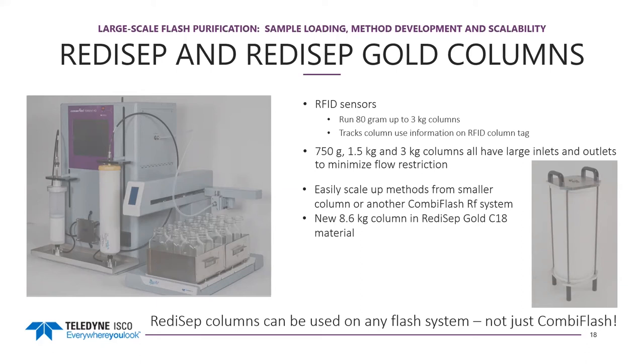All of these columns can be used on any flash system — not just on the CombiFlash, the next gen, or the RF+. You get the advantages of RediSep Gold media, including spherical particle size and smaller particle size for maximum loading. Going from RediSep regular to RediSep Gold material, you could double the amount of compound you're loading just by changing the stationary phase material, with potentially even greater gains when switching from other manufacturers' media.